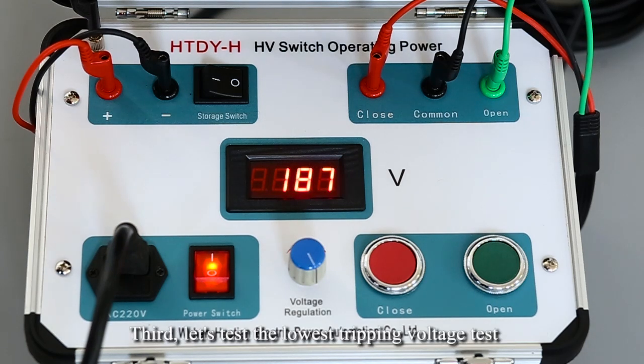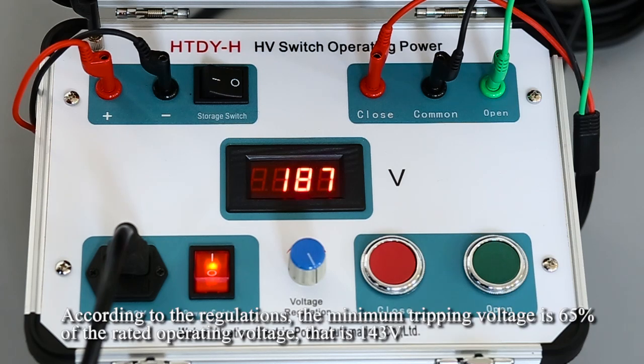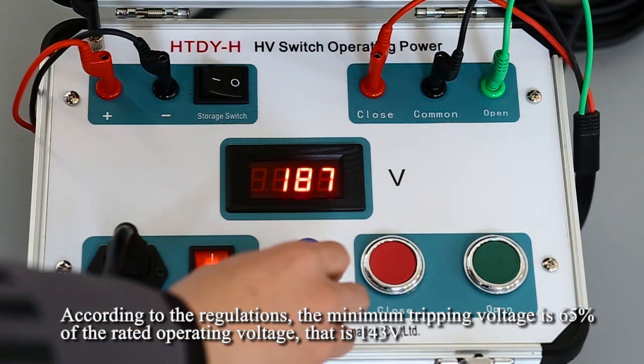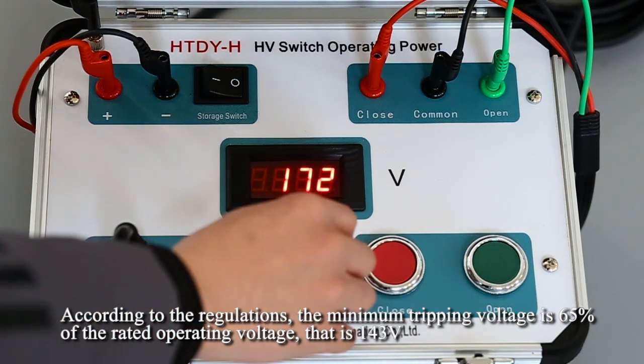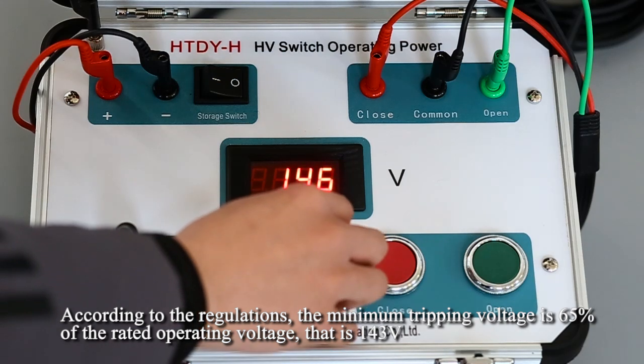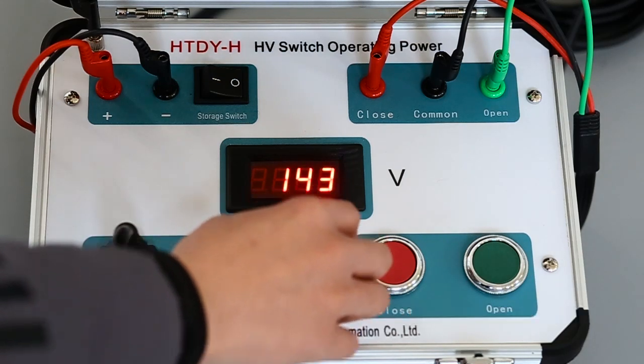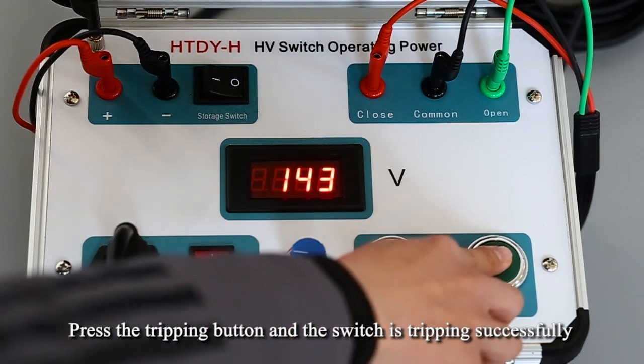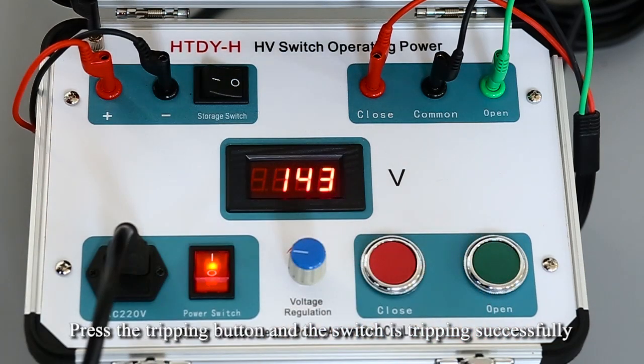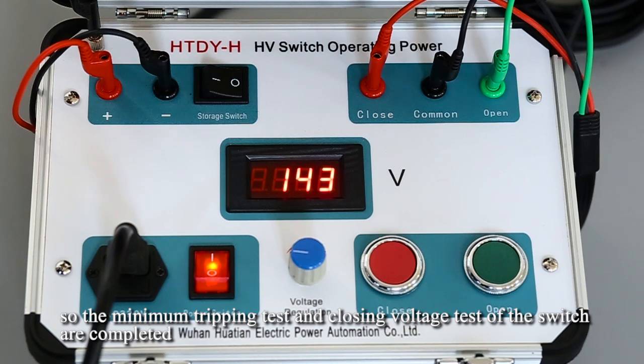Third, let's test the lowest tripping voltage. According to the regulations, the minimum tripping voltage is 65% of the rated operating voltage, that is 143 volts. Press the tripping button and the switch trips successfully. So the minimum tripping voltage test and the closing voltage test of the switch are completed.